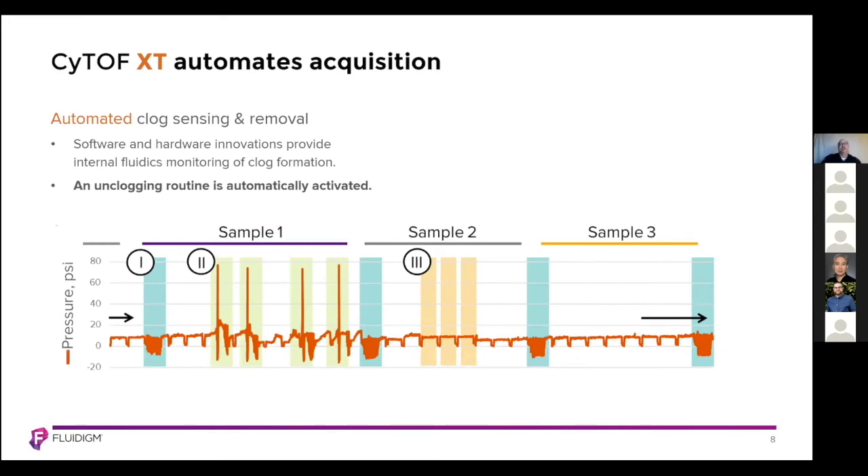Another feature of the CyTOF XT is automated clog sensing and removal. Anyone who has used our CyTOF systems may have been troubled with samples getting clogged. That is now dealt with automatically. We have software and hardware on board that monitor pressure changes in the fluidics, monitor clog formation, and when PSI levels elevate, an unclogging routine is automatically activated.